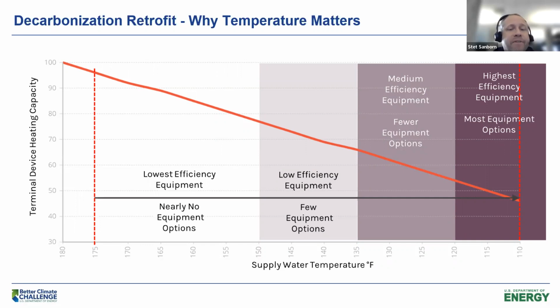So the first step we went through on this project: over an entire heating season, every two weeks we reduced the supply water temperature. We call this a wintertime thermal stress test, or a wintertime supply water reset test. The idea is essentially to run a limbo on your building's heating hot water temperature—how low can you go and still meet your heating demand. The key is to let everybody know this is happening and make sure people have an opportunity to raise a flag if certain spaces aren't able to meet comfort levels.